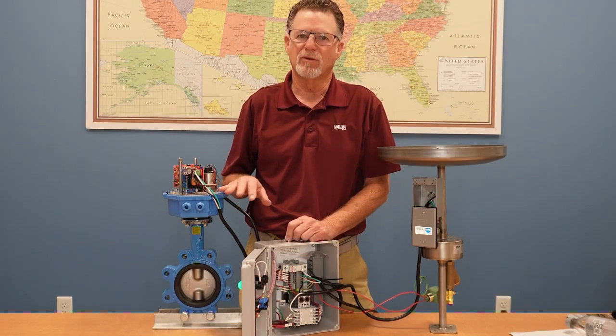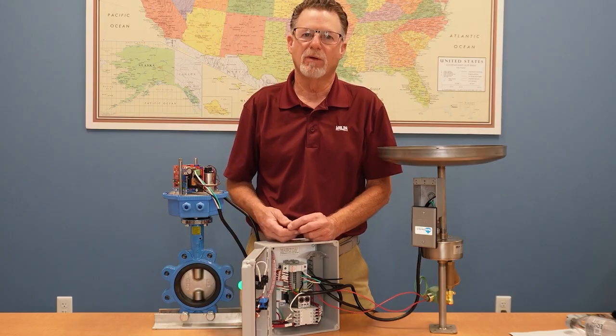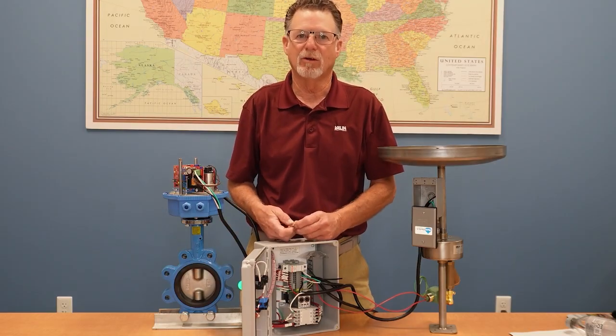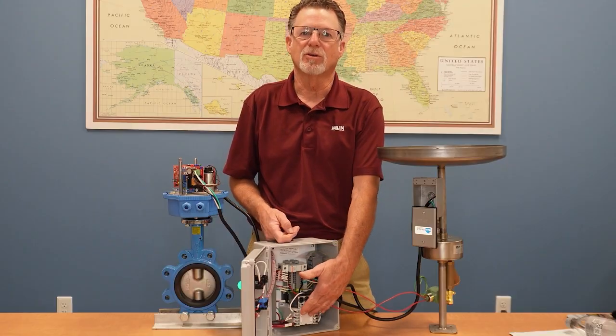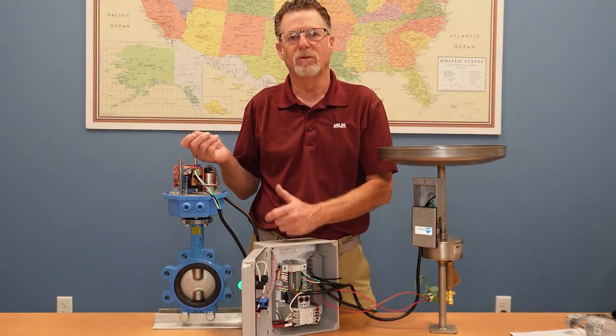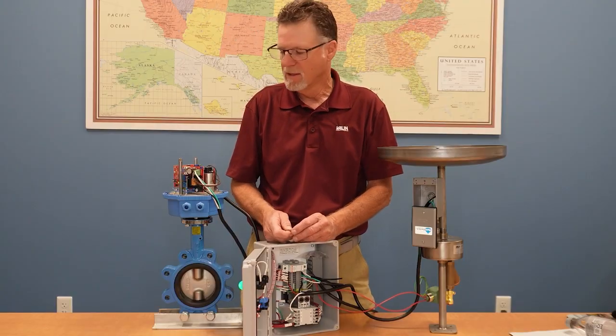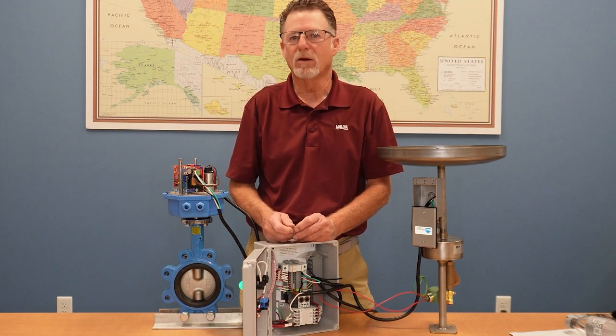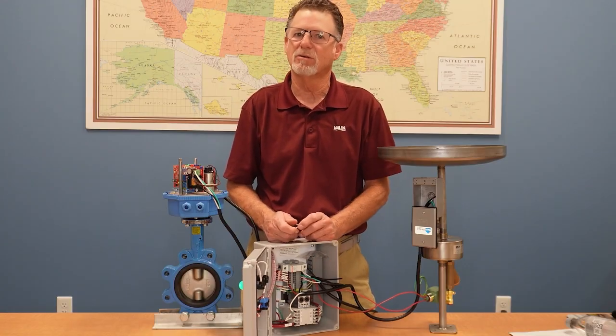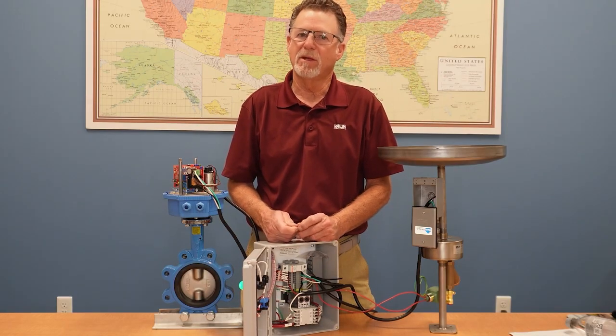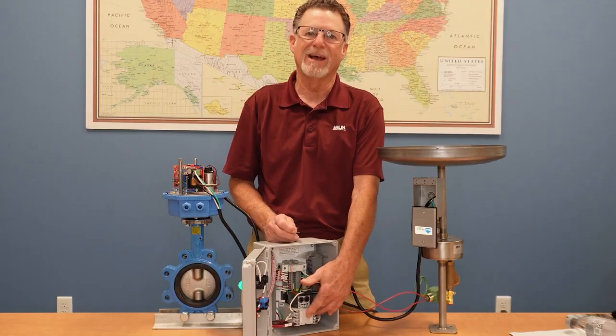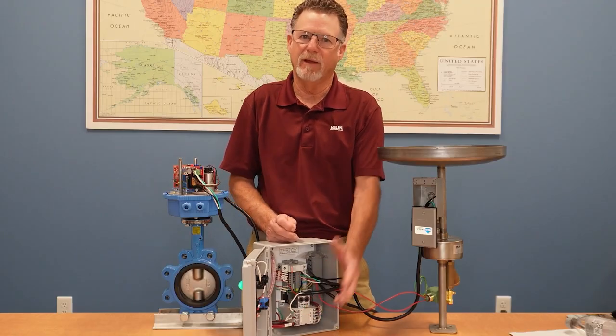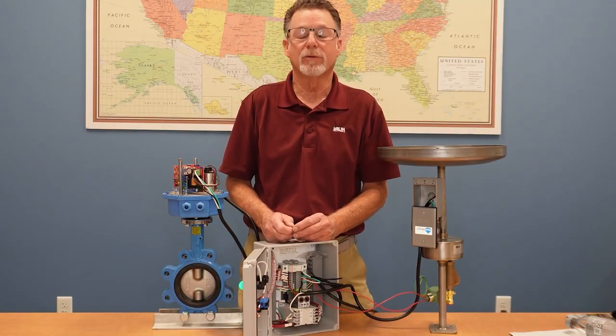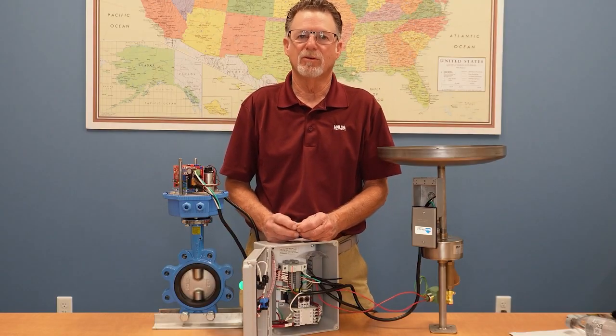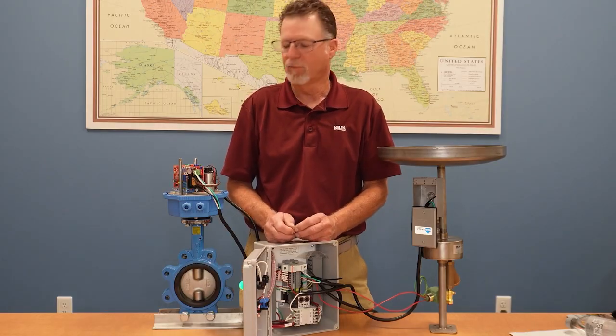If you're going to drive a pump, you have to use an interposing relay. A starter relay, a high current relay. This becomes your control signal to trip the coil of the high starter relay. Most pumps, I have people say, oh, it's only 8 amps and this is 10 amp. That's true. But when you start that pump, it might be a 30 or 40 amp inrush load that's required. And this relay will not take it. You will damage it and have to spend another $400 for a new one. So please make sure if you're doing pumps, use an interposing high amp relay.